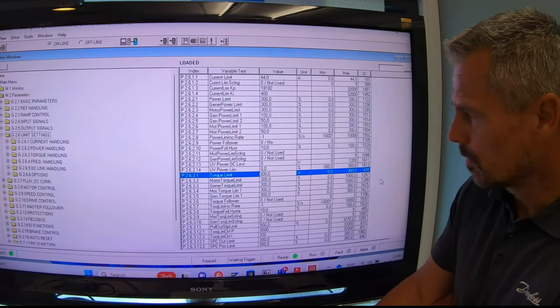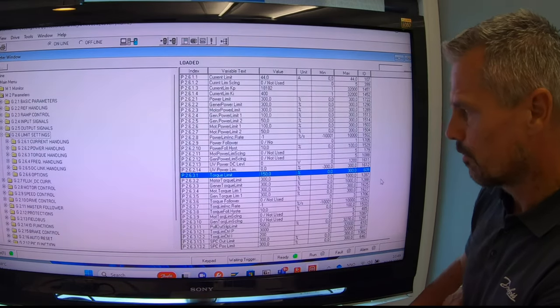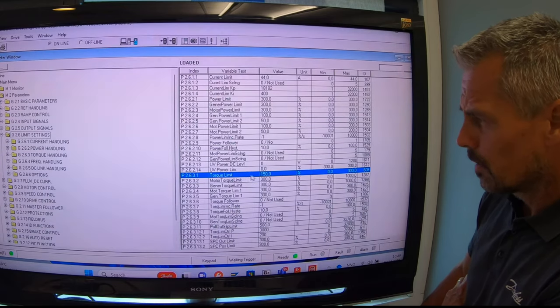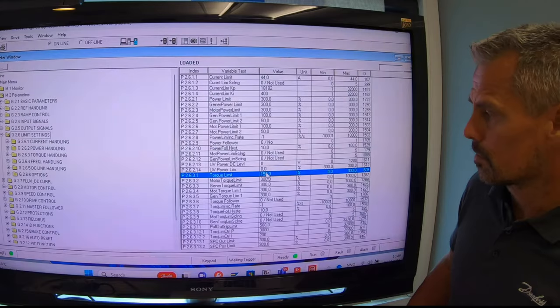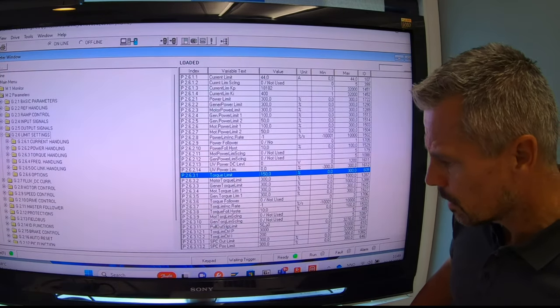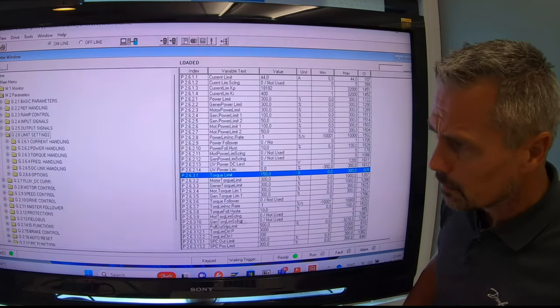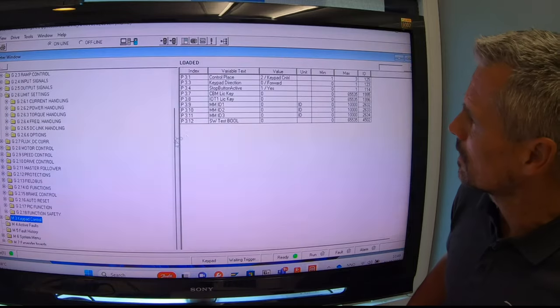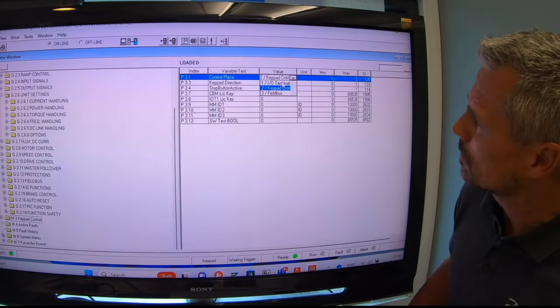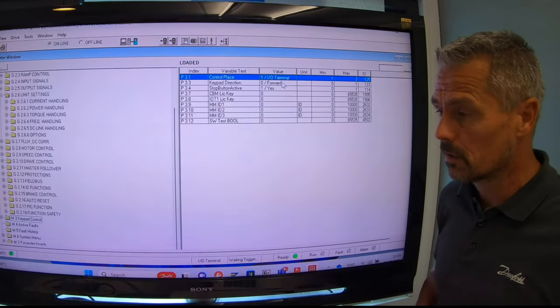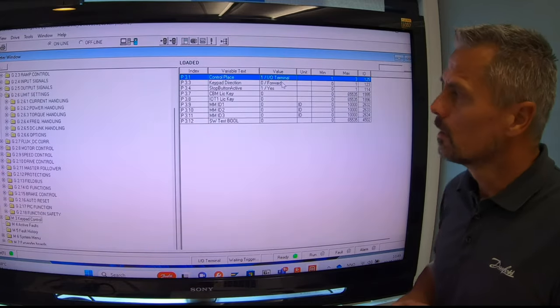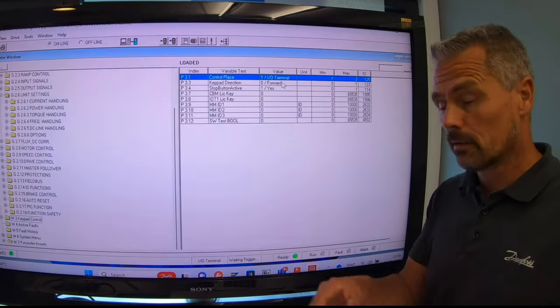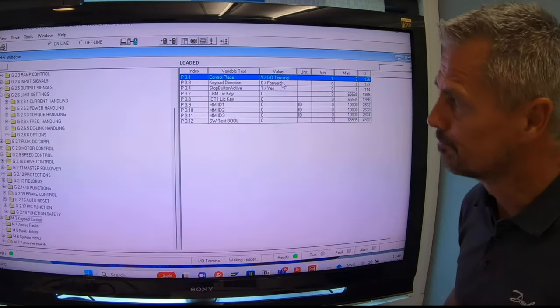The torque limits here sits to 300% default. That's quite a lot. During the tuning, the most important thing is that they are not too low. 300 is a little bit big, so in a real life big scenario, maybe you put 150. And the torque limit will then be for both the braking and the acceleration. Another thing, when you run from the laptop computer, you maybe select that you have IO control so that you don't get the fault that the keypad is not there. I am now running on the CAN bus, so I don't have to remove my keypad.